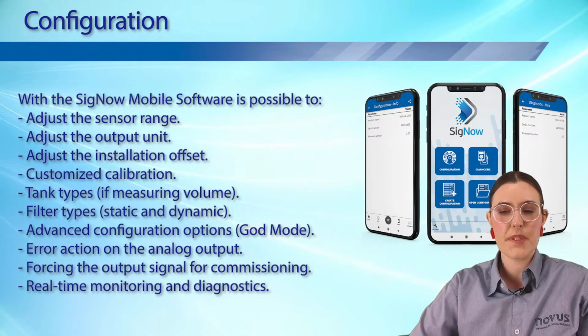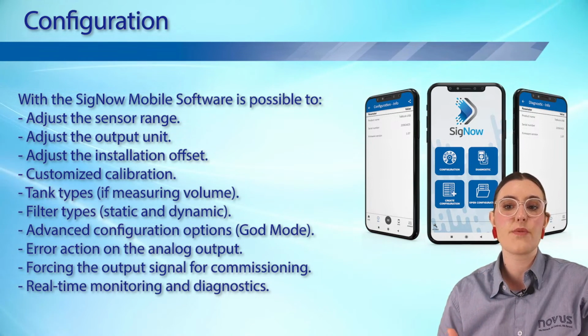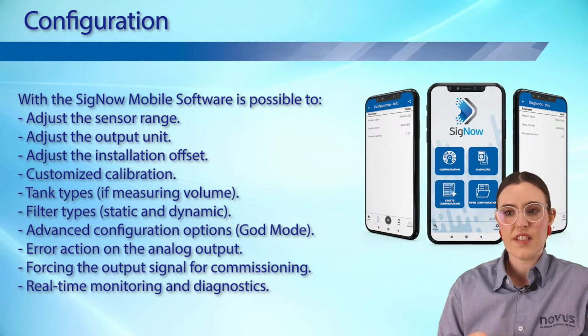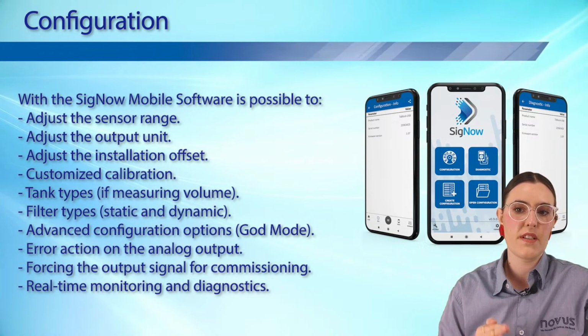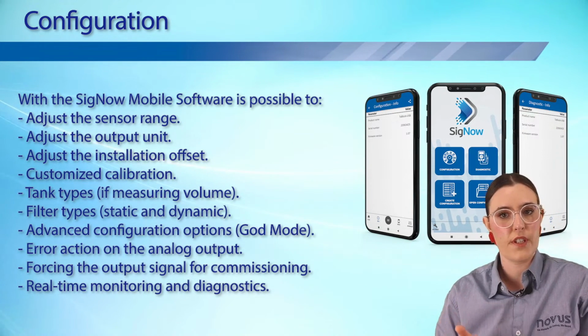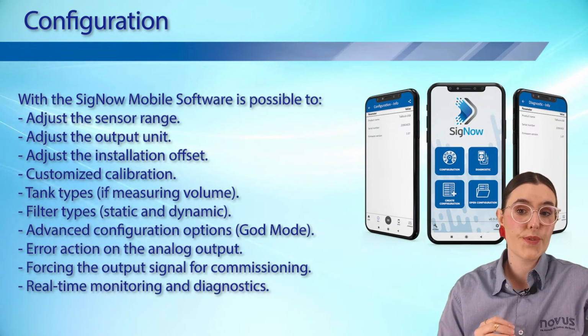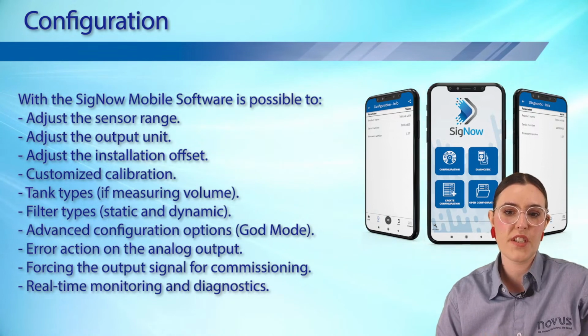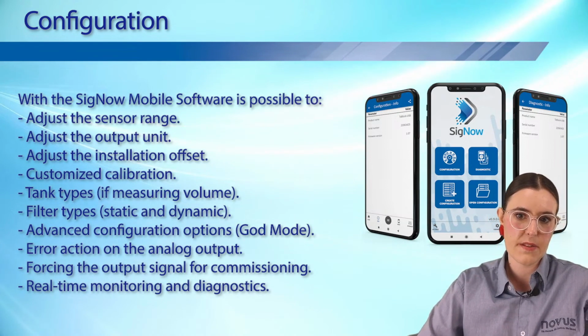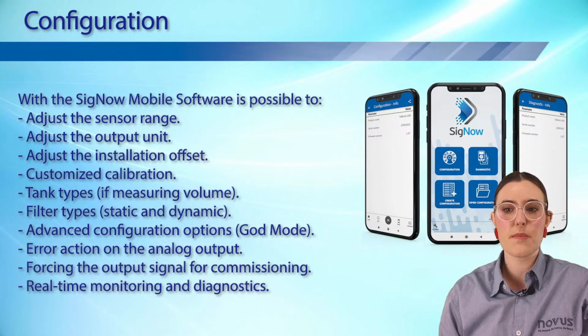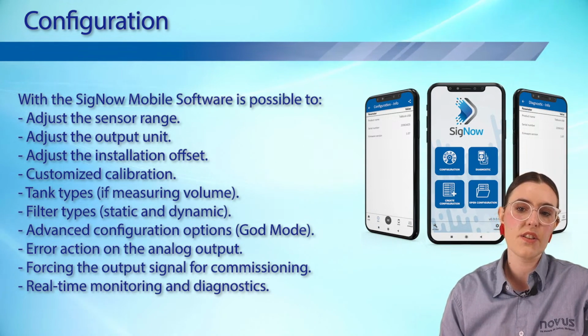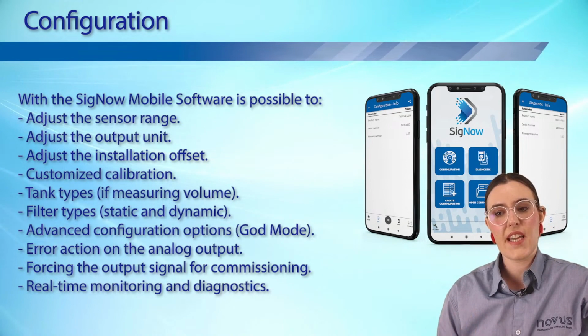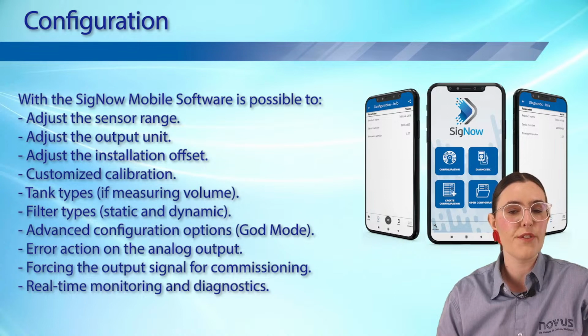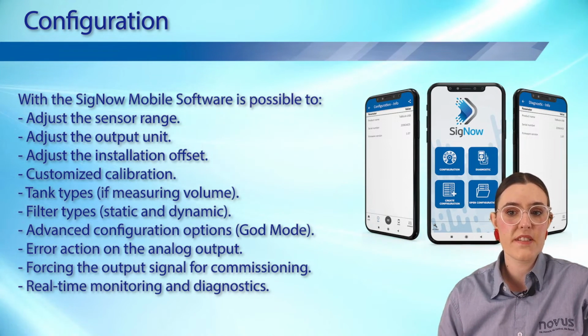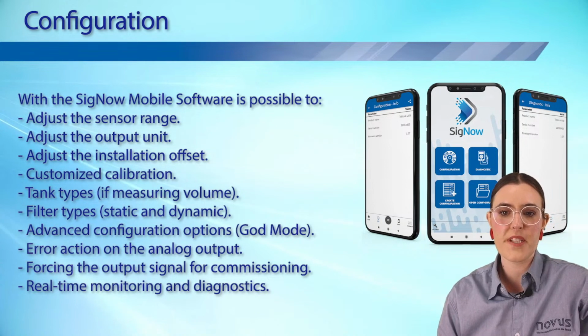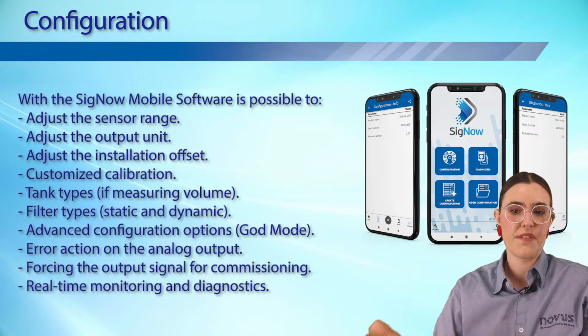Commissioning is facilitated because for simple applications, only a few interactions are required in the app. Just enter the tank height and choose the unit to be retransmitted: level, distance, or volume. Finally, two very useful functions are output forcing for commissioning, and real-time monitoring and diagnostics. With output forcing, it is possible to check on the device reading the analog signal if everything is okay with an indicator or control device, or even with TL400-I itself. The measurement diagnostic allows the verification of measurements in real time, permitting the fine-tuning of the device.